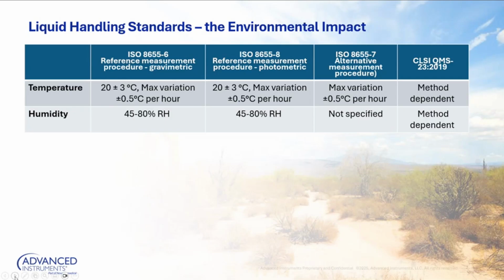Humidity is another row that we want to take a peek at. Air displacement pipettes are very dependent on humidity. According to ISO 8655 Part 6 and Part 8, they advise that your laboratory should have a constant humidity of 45 to 80%. So you walk into the laboratory and you feel like you're in a sauna, because you can feel the moisture in the air. Air displacement pipettes love having a moist environment to work in.